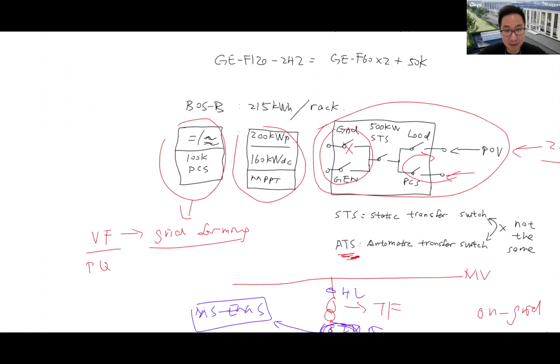So the entire thing is completely off-grid. The only thing you have is maybe generators, only used when necessary. Our PCS will be working in the grid forming VF mode and taking power from solar, from our MPPT module. We highly recommend you use our MPPT module. High efficiency, that's one thing. Another thing is AC coupled PV will not be able to charge our PCS when off-grid. That's one of the drawbacks, because most of the string inverters only work in PQ mode, that's the grid following.